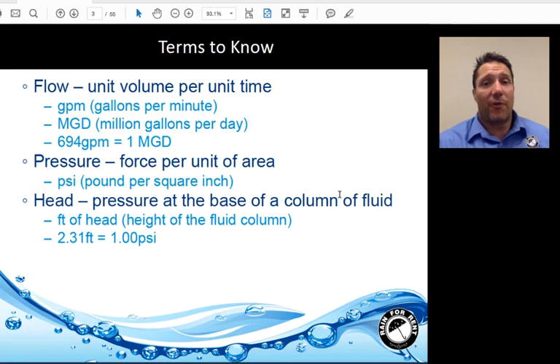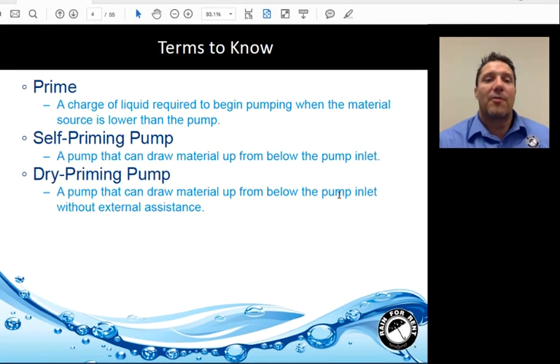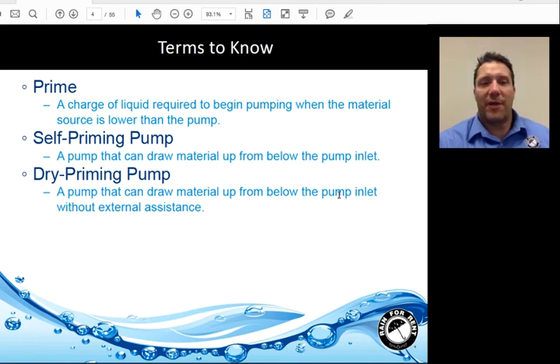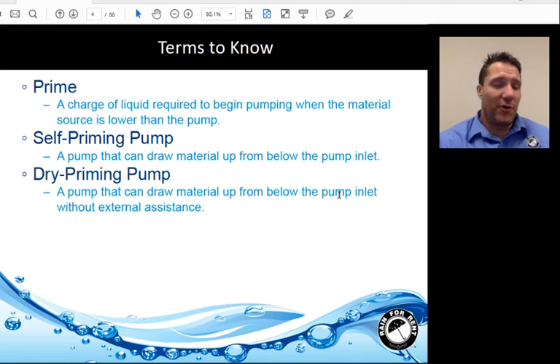The column of water doesn't matter if it's 4 inches wide, 4 feet wide, or a mile wide — it has to do with the vertical height of the water. Prime is the charge of liquid required to begin pumping when the material is below the pump. Self-priming pumps can draw material up from below the pump inlet. A dry-priming pump can draw material up without any external assistance. A contractor pump is an example of a self-primed pump — you need to first fill the volute with water manually. With a dry-priming pump, you put the suction hose in, turn the pump on, and the pump will prime itself.